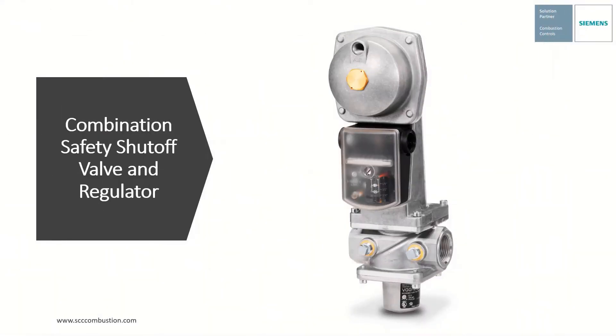The SKP25 is the Siemens combination safety shutoff valve and regulator. Because of the unique combination of one device being a safety shutoff valve and regulator, the sizing is different than what you may be used to. The sizing of a standalone safety shutoff valve minimizes the pressure drop across the shutoff valve. The sizing of a regulator considers the inlet pressure and flow to specify a regulator orifice size.